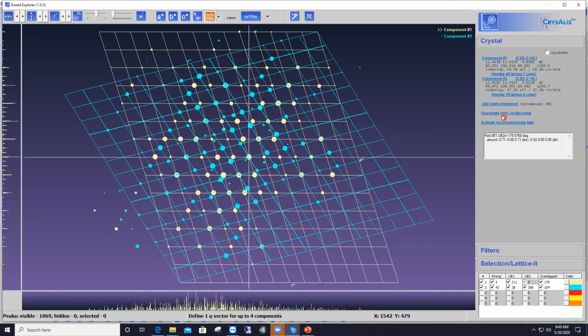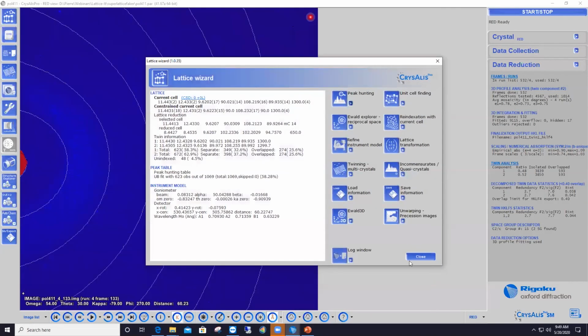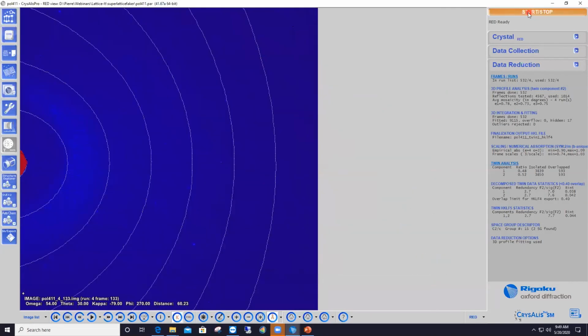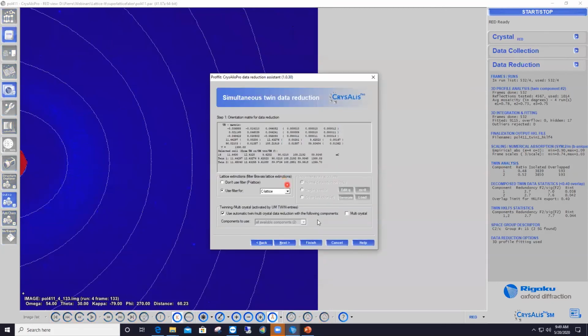And then once you get out of it, this is basically all you need to do in the reciprocal space viewer, and everything is done in there. And once you've done that, and you go to your data reduction dialog by going to start, stop, and data reduction with options, this feature here that is completely grayed out says incommensurate structures. This will be automatically enabled if you index your diffraction pattern with the incommensurate structure enabled. And so at this point, you just go on with processing the data set with the proper Q vectors, and CrysAlisPro will generate for you the proper reflection file.